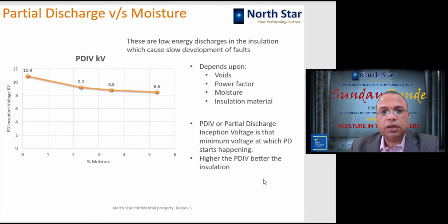Yes. Okay. So in order to have a good, electrically robust insulation system, it is important that the PDIV, or partial discharge inception voltage, should be as high as possible. Okay. If moisture is there in the transformer insulation, then this ability of pushing the PDIV to a higher limit gets compromised, and partial discharges start happening at a lower voltage also. So chances of failure of the transformers are very high.